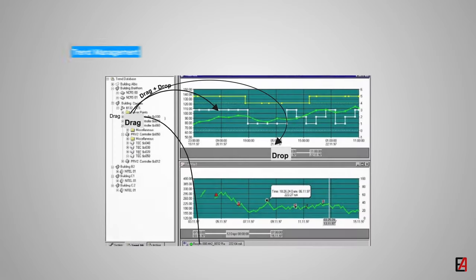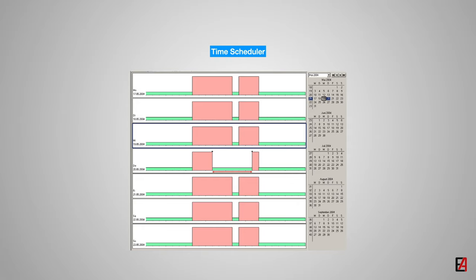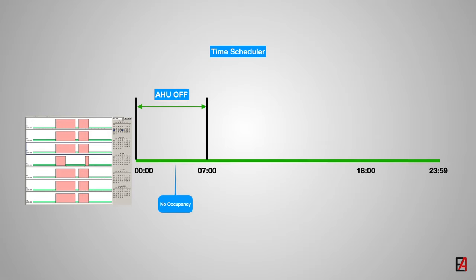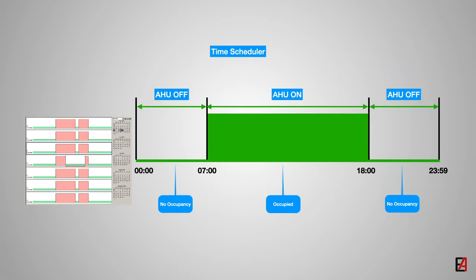In order to identify if the equipment is performing efficiently, BMS provides a trend management functionality. It displays raw values in a time-based graph. These graphs can be exported into an Excel format for analysis. Since the BMS system is also referred to as an energy management system, it provides a functionality to control equipment based on time, known as a time scheduler. The time scheduler lets the operator decide when to turn on and turn off the equipment. For example, the air handling unit serving an office can be programmed to turn on only during work hours from 7am to 6pm. This is very helpful as equipment can be configured to turn off when there is no occupancy.